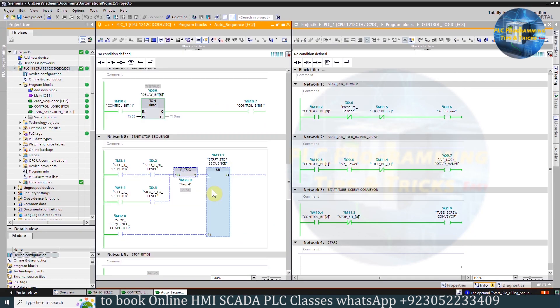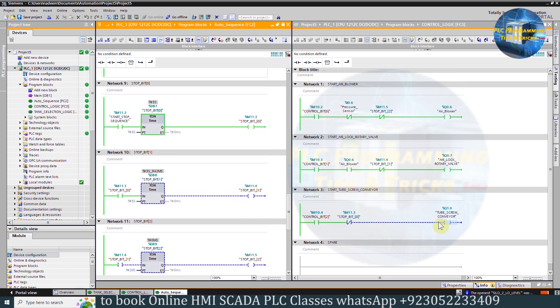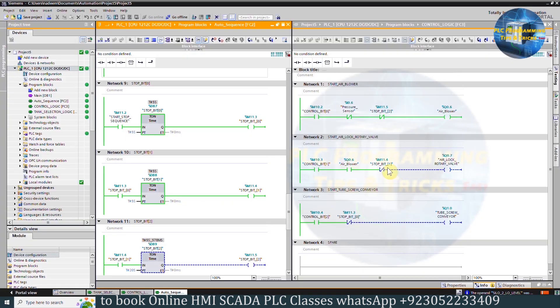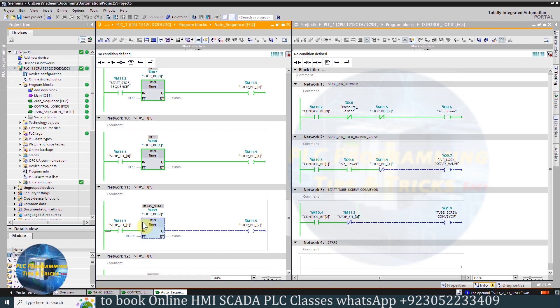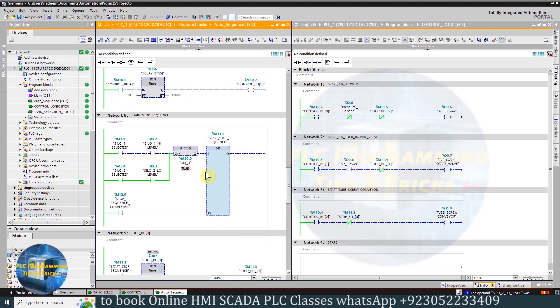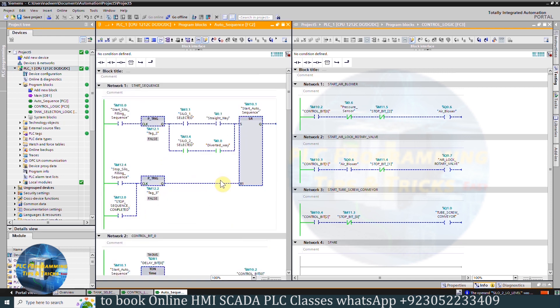In Network 8, we have the logic to start the stop sequence. As the high-level sensor for silo 2 turns on, it will start the stop sequence. As soon as stop bit 0 turns on, it turns off the tube screw conveyor Q1.0. After 5 seconds, stop bit 1 turns on and its normal-close contact opens, turning off the rotary air lock valve Q0.7. After the next 20 seconds, stop bit 2 turns on and turns off the air blower Q0.6. Finally, the stop sequence completed bit M12.0 turns on, resetting the start-stop sequence bit M11.2 and the start auto-sequence bit M10.1 — the whole sequence stops after silo 2 is full.